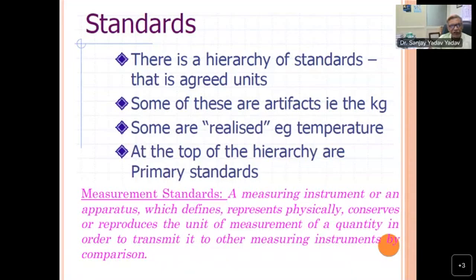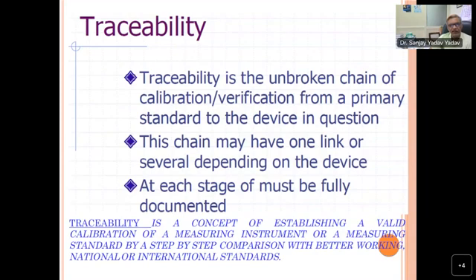Standards. There is a hierarchy of standards that is an agreed unit. Some of these are artifacts, like the kilogram, and some are realized, for example in temperature. At the top of the hierarchy are primary standards. A measuring instrument or apparatus which defines, represents, physically, conserves, or reproduces the unit of measurement of a quantity, in order to transmit it to other measuring instruments, is called a measurement standard. Traceability is the unbroken chain of calibration verification from the primary standard to the device. But this chain may have one link or several, depending upon the device. Each stage must be fully documented.